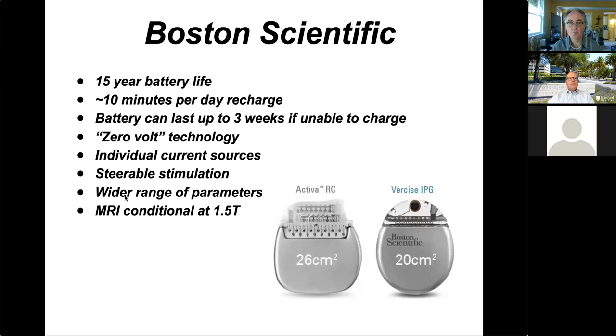So the Boston Scientific system, this is with comparison. So this is a rechargeable system, the one that I most commonly use. This is a comparison to Medtronic's Activa RC, which is their standard rechargeable system. So it's smaller, has in my opinion a nicer form factor where there are no edges. It's almost perfectly round. It has about a 15-year battery life, about 10 minutes per day to recharge it. So there's a pretty simple recharging system with a strap that goes around the shoulders that puts the recharger over the device. It beeps until it finds it. Once you've found it, then it stops beeping, and then it double beeps when it's done. And I usually encourage patients to take about 10 minutes or so per day to recharge it so you don't forget.